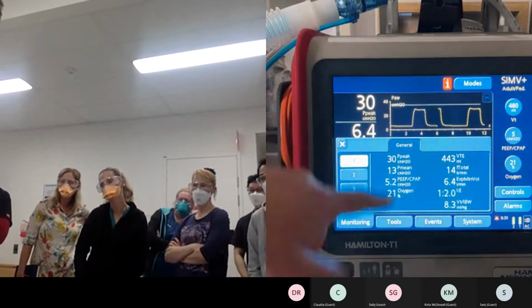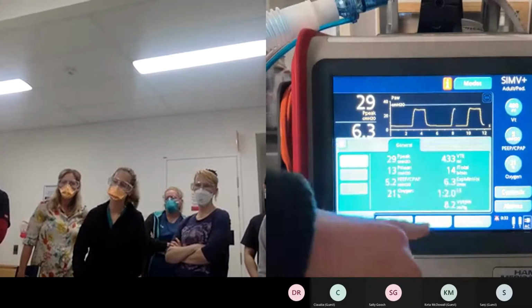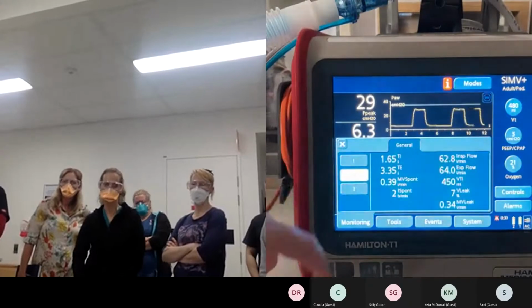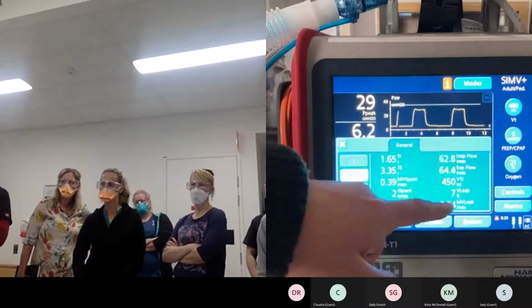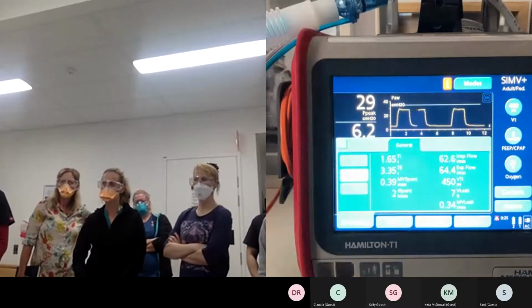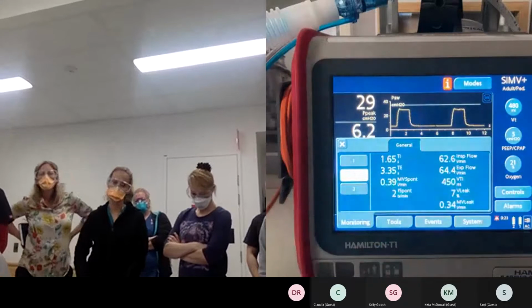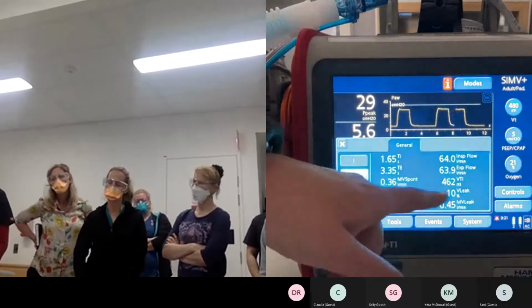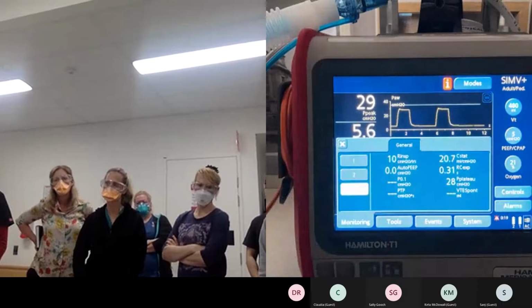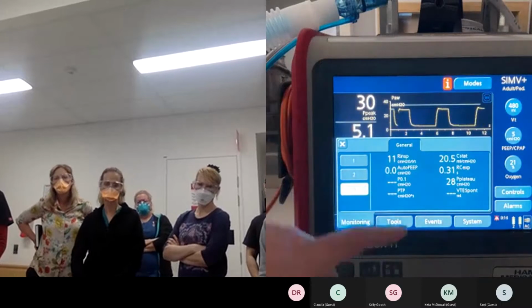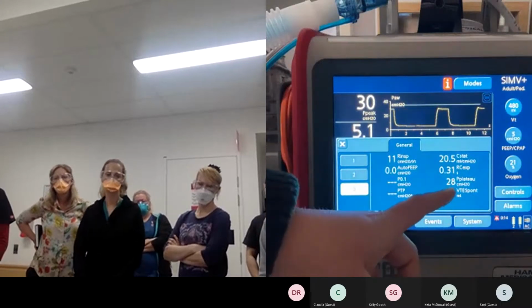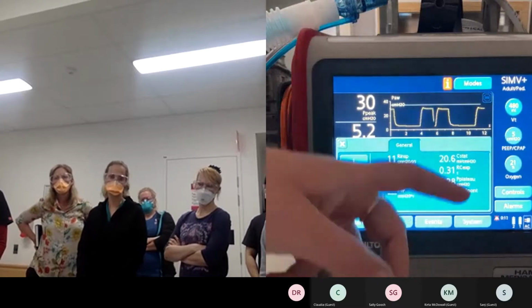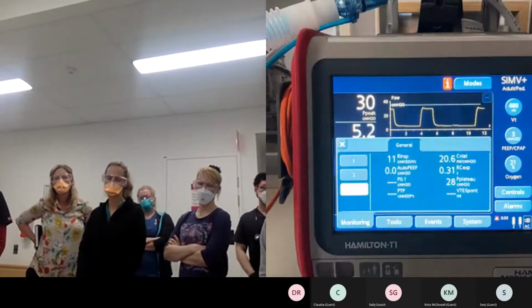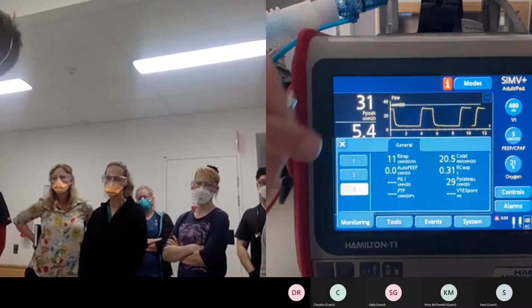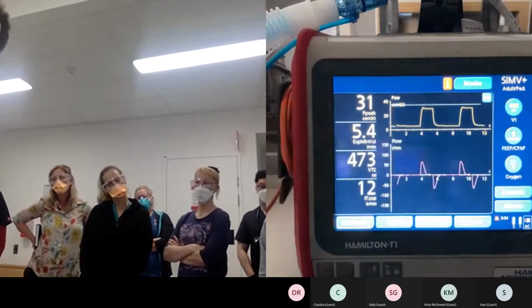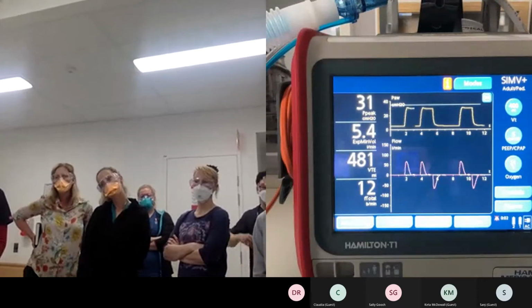So the first page is your pressures and your minute volume. Page 2 is your I time and your flow, and then you've got your leak. Okay, because of the turbine feature, it does have the ability to pull in quite a bit to compensate for leak. And then page 3 is your resistance and compliance. It will give every now and then a plateau pressure, but it may not be there consistently. It's always a calculated plateau pressure. And I'll show you how you could mimic one to measure one though, okay?